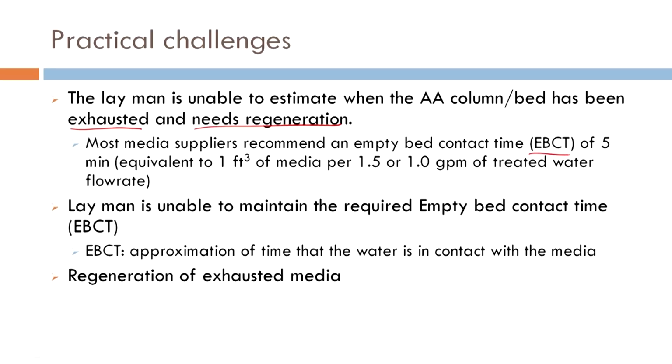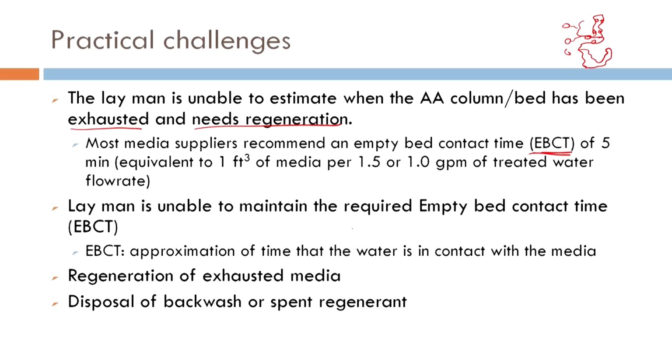Empty bed contact time, as in the water has to stay in contact with your adsorbent, let us say, so that the molecule can diffuse onto the surface or into the pores and get adsorbed onto the pores, let us say, right. I have different pores and such out here. The water has to, or the molecule has to diffuse into it. That is why I need to provide a contact time, let us see, right. Again, these are some of the practical challenges.